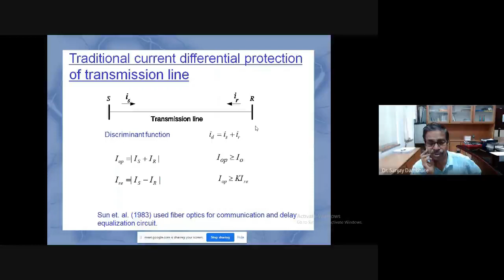And the point is that if that is the case, then why should we not go for the differential protection, even for the transmission network? And the answer is yes, we can go. Earlier, differential protection was not used for the transmission line because there was a difficulty in time synchronization of the data. Because the transmission line is quite long, how to synchronize the sampling of the 2 ends, that was the problem. How to transmit the data from one end to another, that was also a problem.